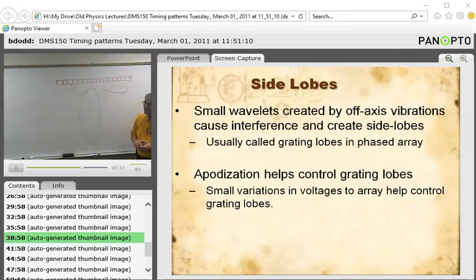Grating lobes are generally caused by when these crystals are hit by an electronic signal. You remember they deform, correct? They're piezoelectric. You hit them with electricity and they'll change shape. It turns out that not all of the shape change is just frontwards and backwards. Sometimes they vibrate a little bit to the side. They're not perfect materials, and so they'll expand not only this way, but a little bit sideways. That's what's going to build up and start creating these grating lobes. So all of these different crystals are firing off, and all of them have this little bit of expansion sideways, and it's going to help to create grating lobes.